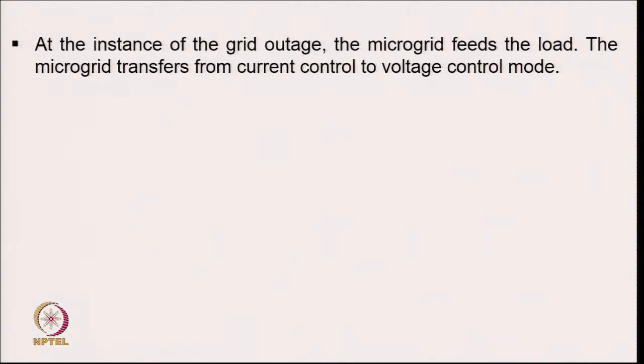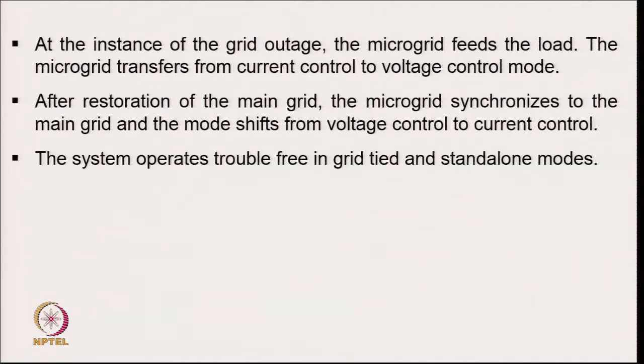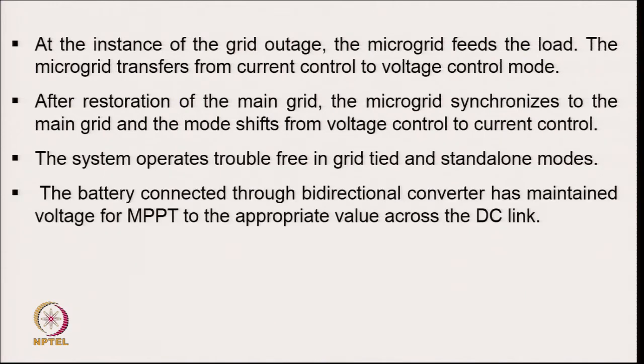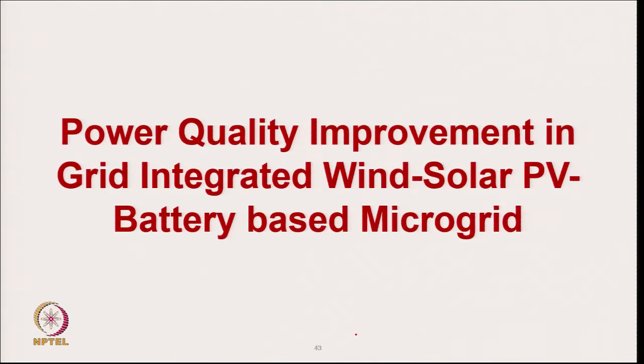At the instance of grid outage, the microgrid feeds the load and transfers from current control to voltage control mode. After restoration of the main grid, the microgrid synchronizes to the main grid and shifts from voltage control mode to current control mode. The system operates trouble-free in both grid-tied and standalone modes. The battery connected through a bi-directional converter maintains voltage for MPPT at an appropriate DC link voltage. Grid current THD and voltage THD have been observed less than 5 percent as per the IEEE 519 standard.